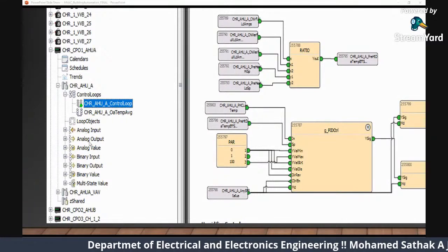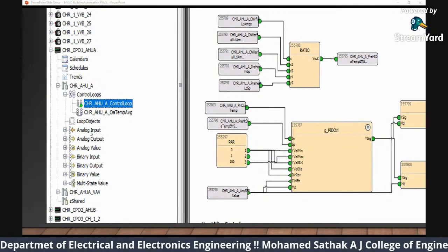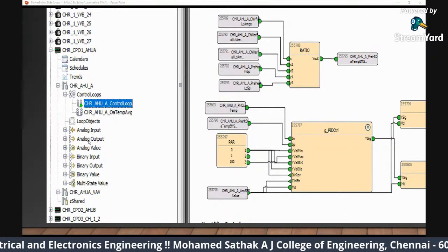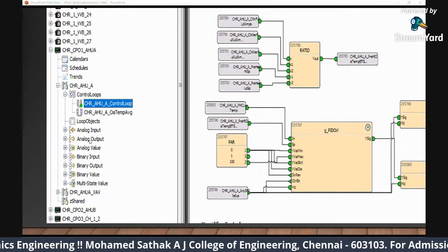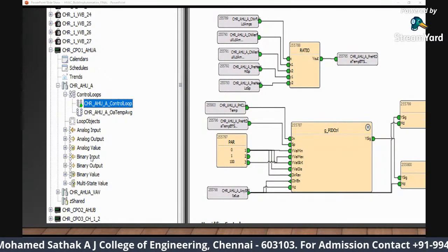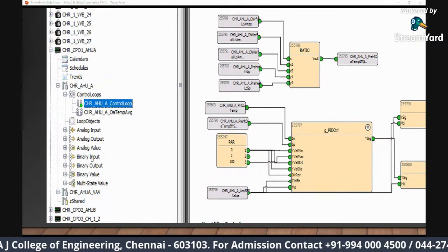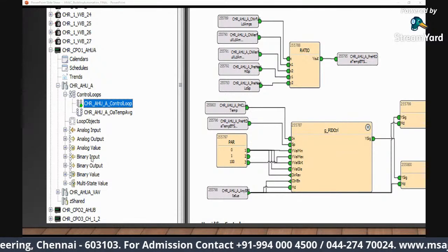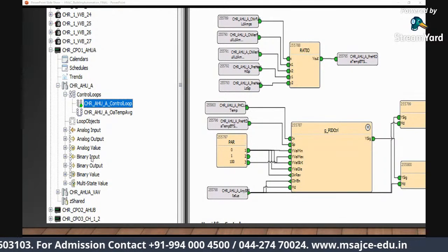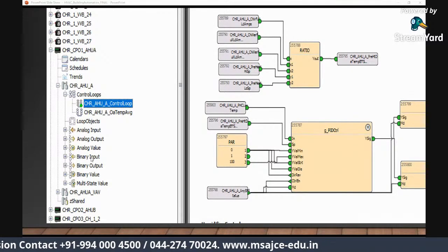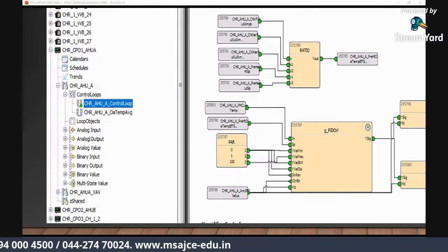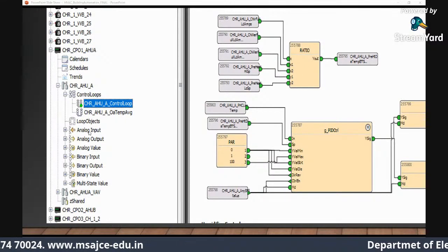left, analog input, analog output. All your inputs will be your temperature, pressure, humidity. Analog output will be your valve dampers. Binary input will be your statuses of your fan, if the fan is running. Anything zeros and ones are called binaries. Binary output will be a fan and pumps. Anything that is modulating 0 to 100 are called analog.